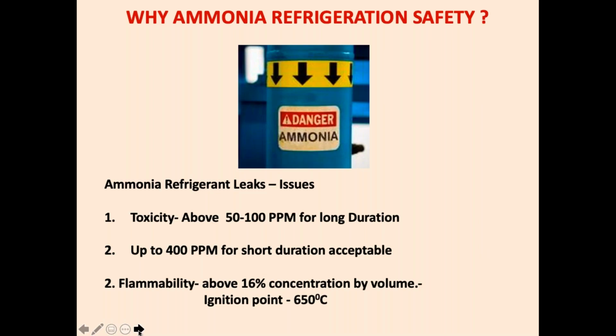Now, why ammonia refrigeration safety? Because we saw the toxicity of ammonia: exposure above 100 ppm for a long duration is dangerous. Up to 400 ppm for a short duration, nothing will happen, but subsequently it can create serious problems. Especially liquid falling on a person can lead to total burnout of the skin. I have seen a lot of potato cold storages that use bunker coils, and the bunker coils are on the top. If the bunker coil starts leaking, the liquid ammonia falls on a person, and there could be deaths or serious injuries, because the entire skin will be burnt and your bones will be exposed. So liquid is very, very dangerous.